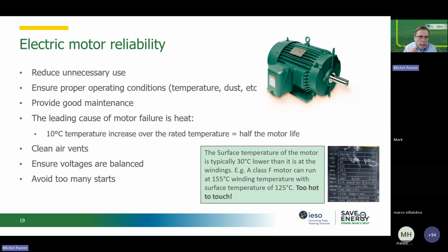Motors do not like heat. So if your motor is not ventilated properly, if it's in an enclosure that's really hot, it will reduce its life expectancy significantly. Most of the motors we use in our buildings are what we call Class F motors. Class F, the different class of motors, is about how hot the winding can run without reducing its life expectancy too much. So a Class F motor will run at its maximum temperature of 155 degrees for the winding temperature. The surface temperature will be typically 30 degrees lower.